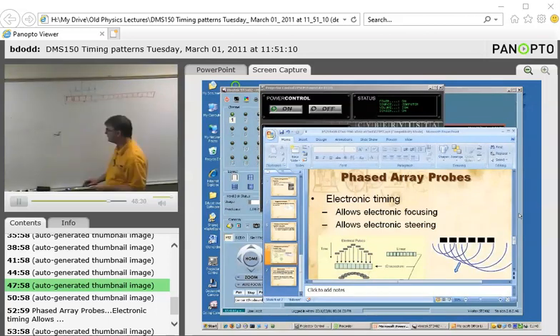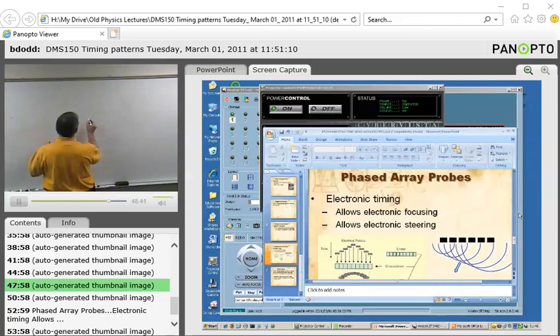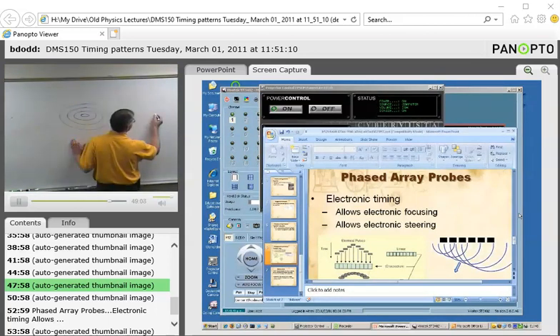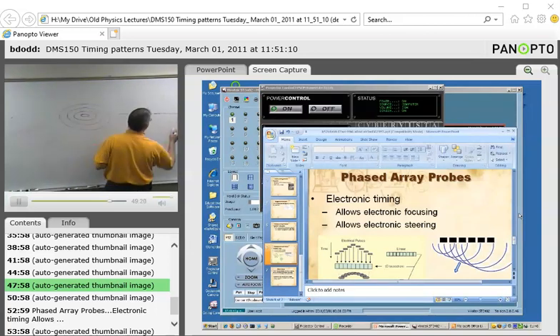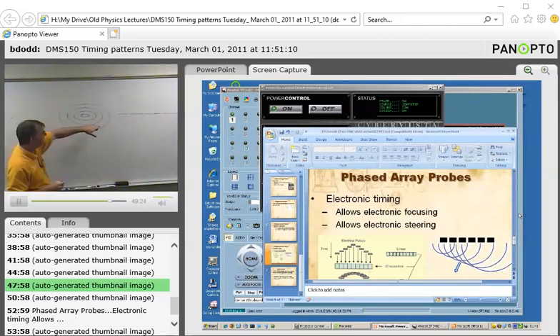So let's talk a little bit now about annular array transducers. Okay, so if we have a crystal and we're going to make our transducer out of multiple concentric crystals like that, all right? And so this one is actually facing out towards you. I have a hard time drawing it on the board so it's facing down like I do my usual crystals. But you could think of it as, we'll try to point it down. I've got my very center one here, and then outside of it, another group and then another group. Maybe I should do this in color. Okay, so we take this and we turn it down, and this is what we end up with.